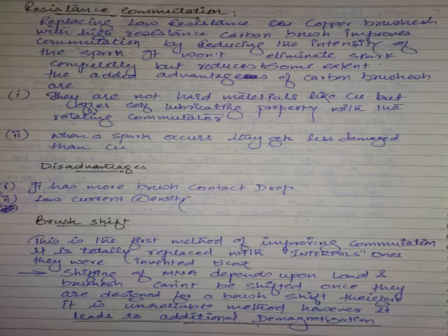That is one advantage. Apart from that, copper material itself is very hard, but carbon brush is smooth in nature, self-polishing in nature. Continuously, when the commutator is running at a high peripheral speed, the surface of carbon is self-polishing. Generally you will put some grease or oil in the bearings in order to reduce friction. Why? The surface should be as smooth, with as little friction as possible. Due to the carbon material, when it is running, the surface becomes self-polishing in nature, so smooth and offers less friction. When it offers good mechanical conditions, definitely sparking will not be there. So compared to copper, carbon brushes are more advantageous when it comes to sparking.